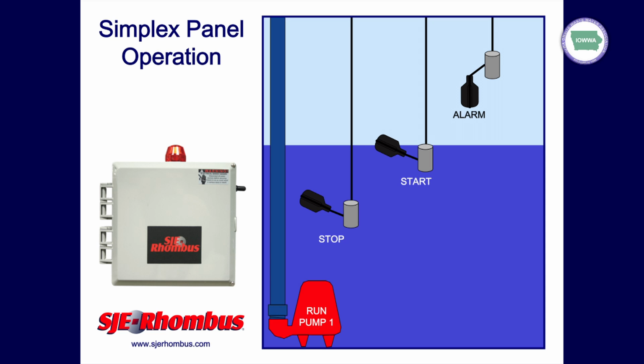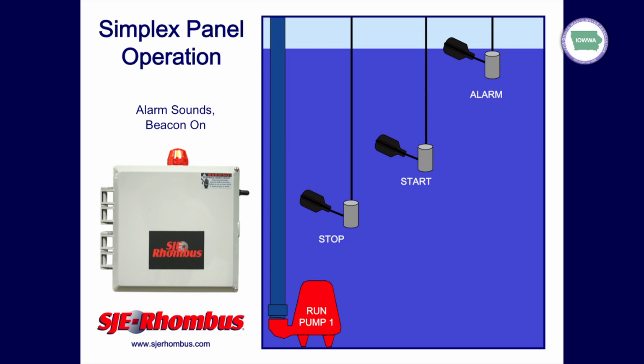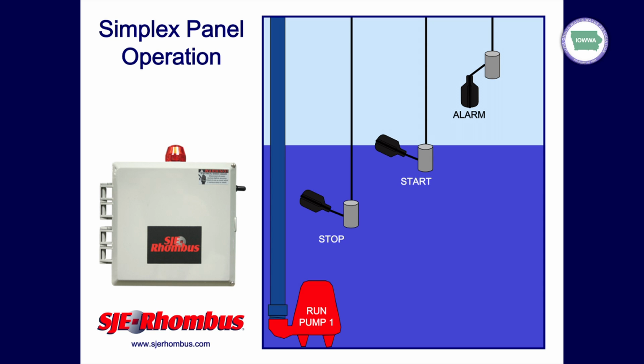We can use this graphic to address something from earlier about the float switch. Go back. When we talk normally open or normally closed contacts in the float, what's the normal position? Normal is hanging down. This float is in its normal position, or normally open. 99% of the floats we sell are normally open, but you can get a normally closed switch. So the contact would be closed when that float is hanging free with no liquid around. Good way to remember it.